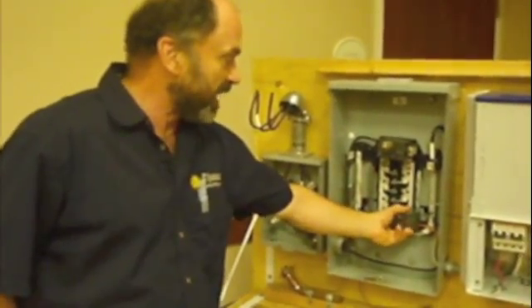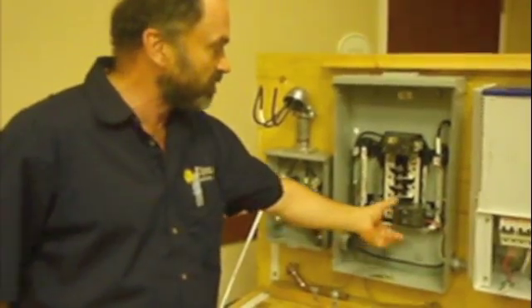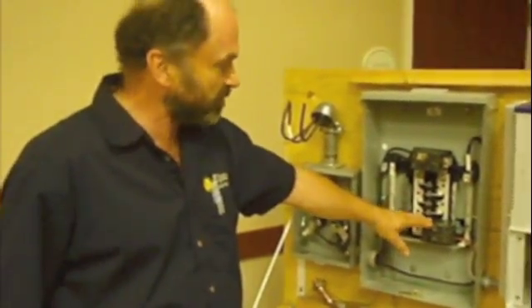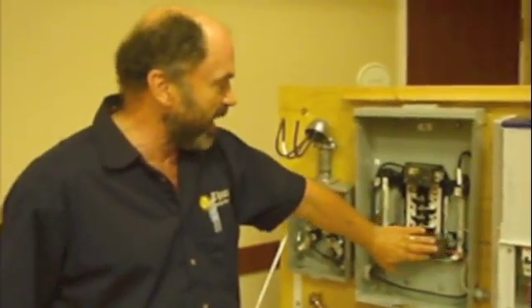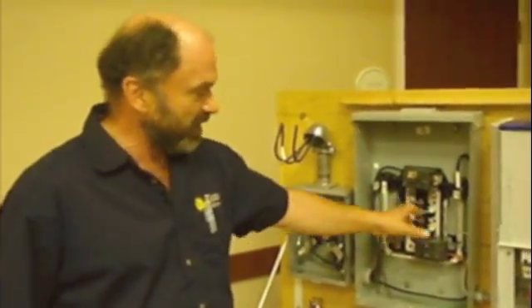We must put that breaker down at the bottom of the bus so we do not overload any part of the bus. This breaker is actually being back fed, feeding onto the bus and then feeding the loads.